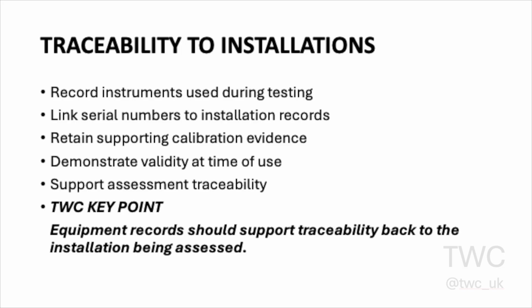An assessor may wish to know not only that an instrument was calibrated, but also which instrument was used on a particular installation. For that reason, organisations should consider how instrument serial numbers can be linked to installation records where appropriate. Being able to trace a measurement back to a specific instrument and calibration record can provide a much stronger evidence trail during assessment.